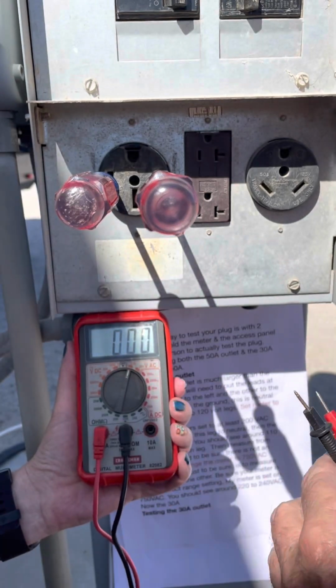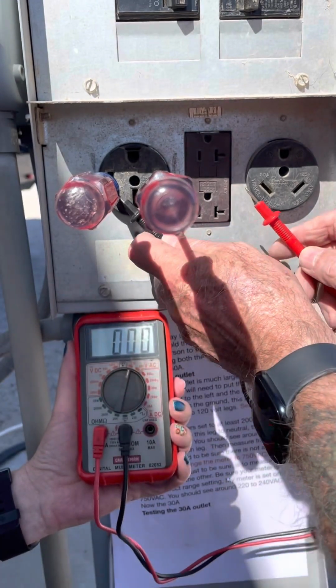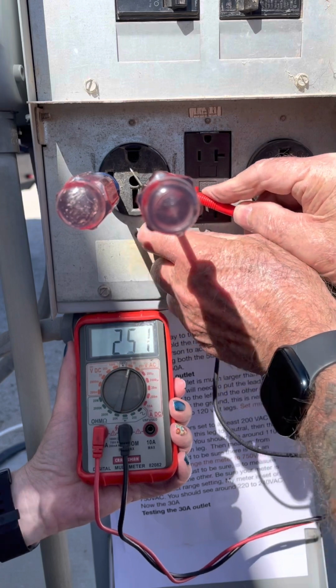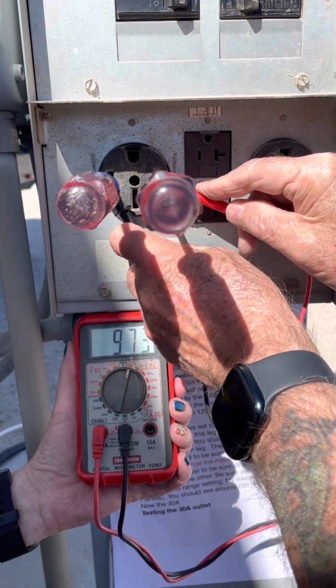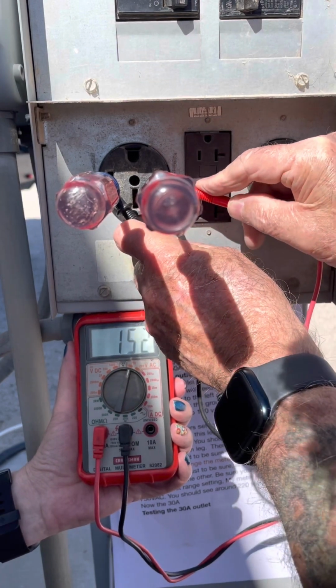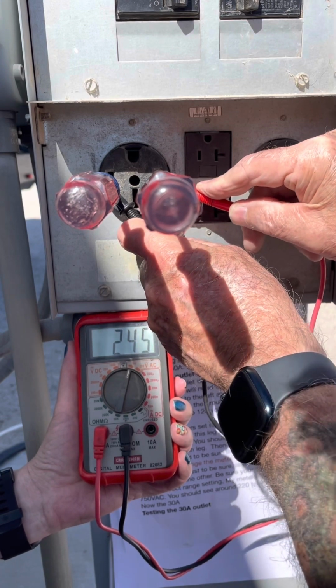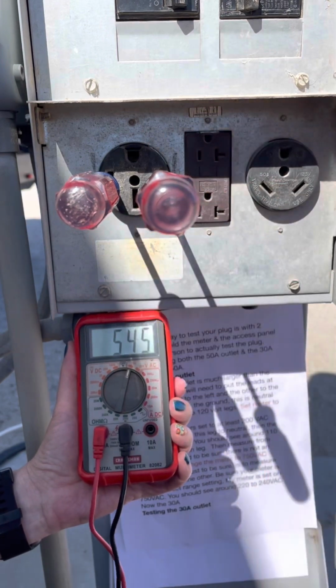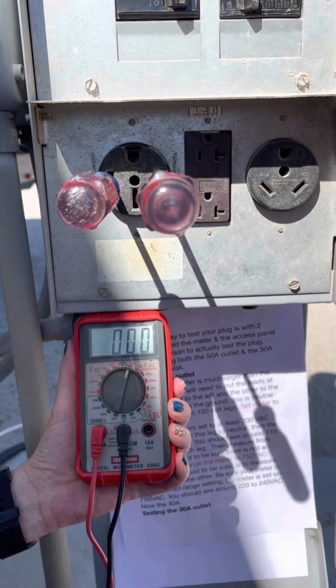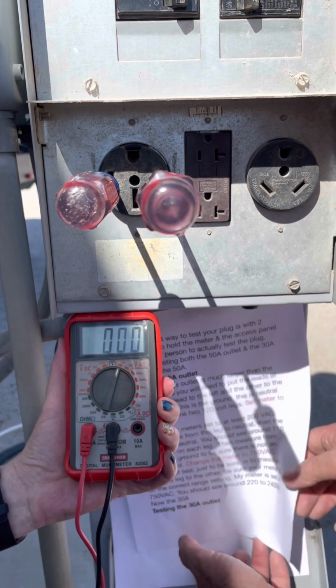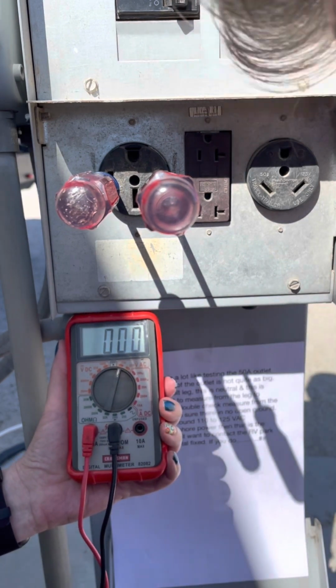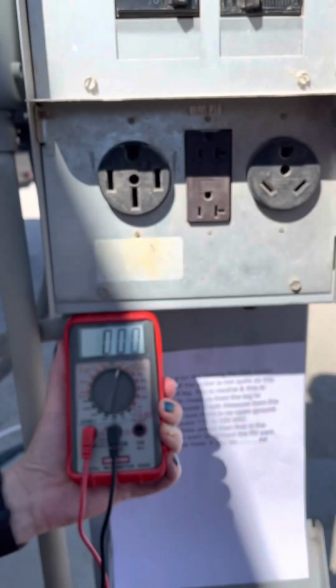Change your meter to 750 volts and measure from leg to leg. And that should give you around 240 volts. So that's the 50 amp outlet. Next, we'll test the 30 amp outlet. We will not need the screwdrivers for that because my meter will reach.